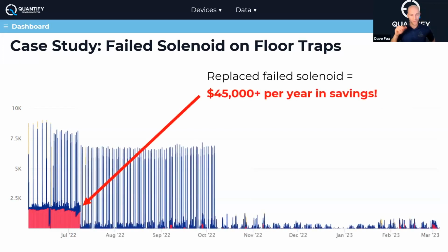We took that data, went into the facility, and applied our experience. I personally went through and found the culprit: a failed solenoid valve. Solenoid valves are meant to provide water to systems, and they're designed to fail open because you want water going to that system, even at a loss to the company, because it needs to protect something. So we fixed that solenoid valve on a Friday in late July. You can see the exact minute it was replaced, and here we are, down to zero.